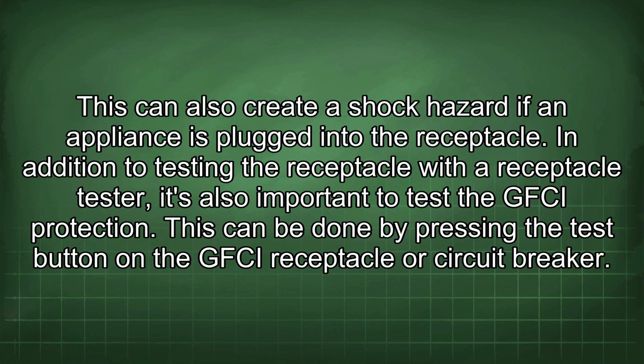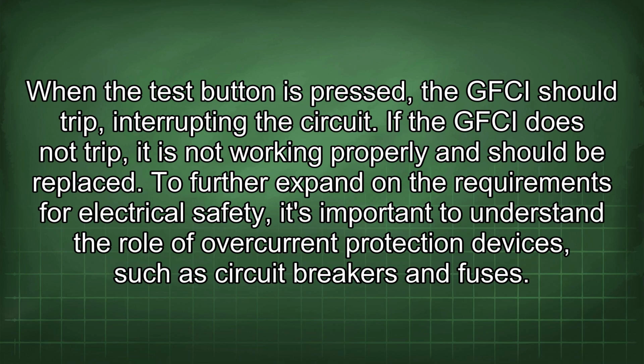In addition to testing the receptacle with the receptacle tester, it's also important to test the GFCI protection. This can be done by pressing the test button on the GFCI receptacle or circuit breaker. When the test button is pressed, the GFCI should trip, interrupting the circuit. If the GFCI does not trip, it is not working properly and should be replaced.